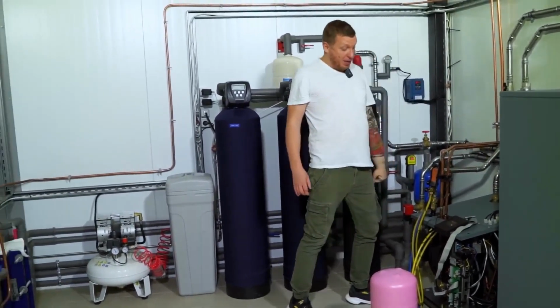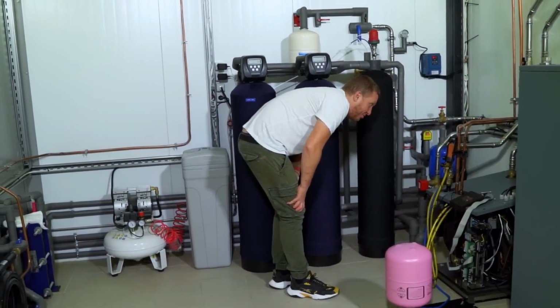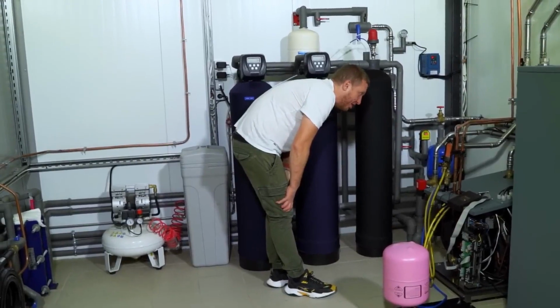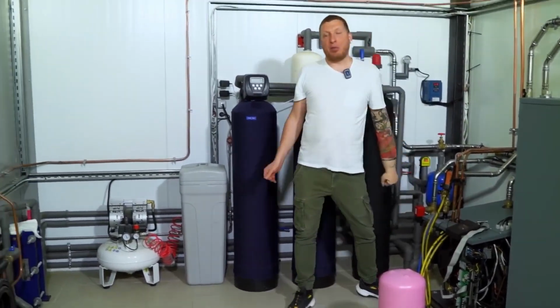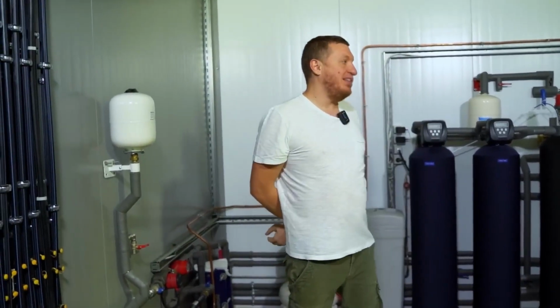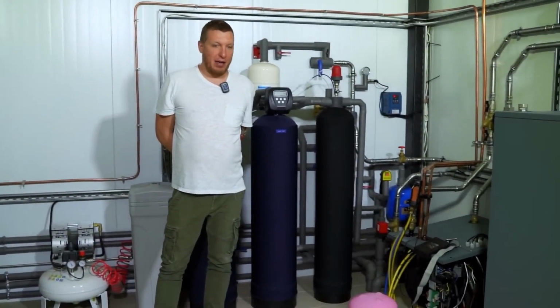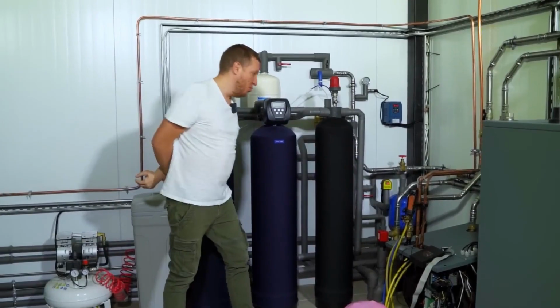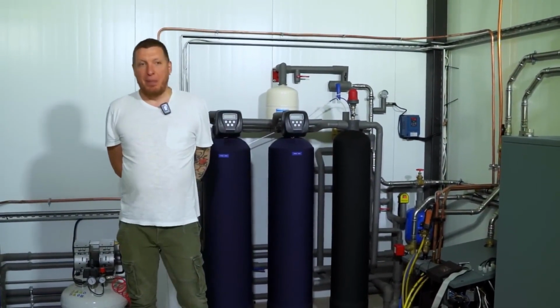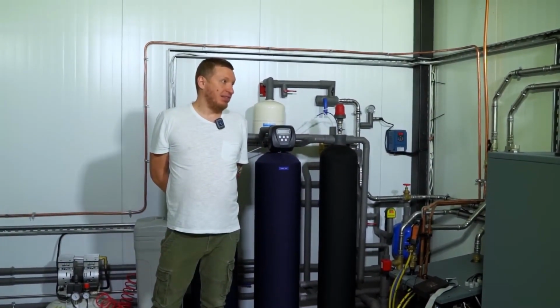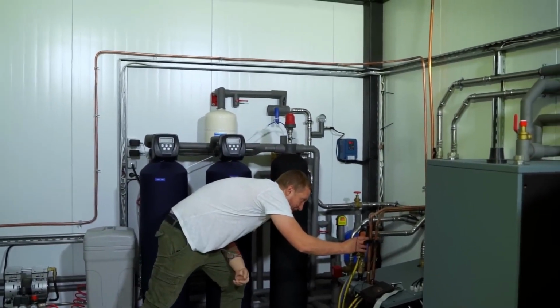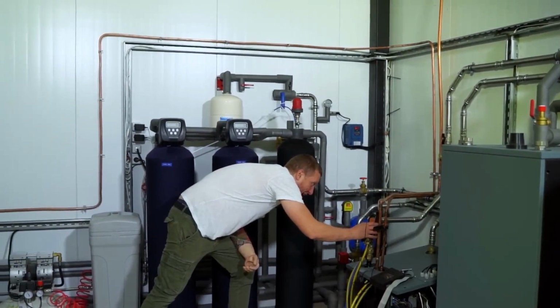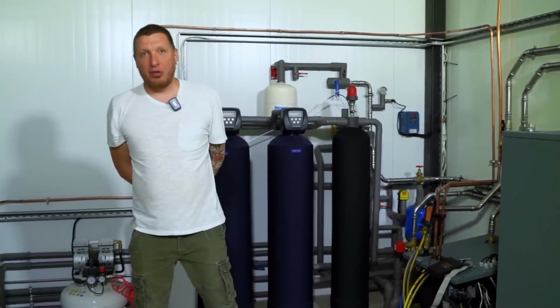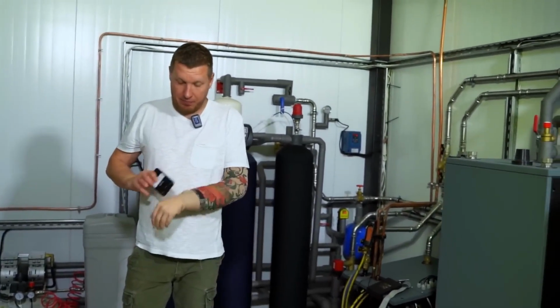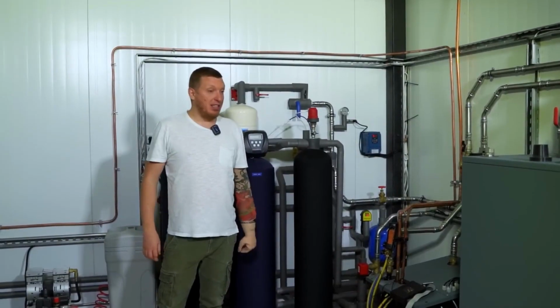So gentlemen, the system has stabilized. We have 5 degrees of superheat and 2.2 of subcooling. And just so you understand what superheat is, there's a relationship between the pressure of the refrigerant and its temperature. It's a constant. So in this case, we look at the fact that we have a certain refrigerant pressure, let's say roughly 7.52 bar on the suction side. At the same time, there should be a certain temperature. Let's say, according to the boiling point, it's 1.5 degrees Celsius. But in our case, it's higher by 6 degrees. Those 6 degrees are what we call superheat. It's like a superheated liquid, but still... Yeah.